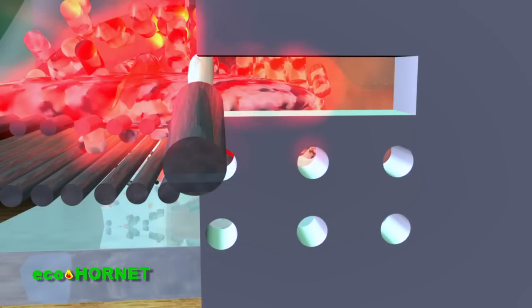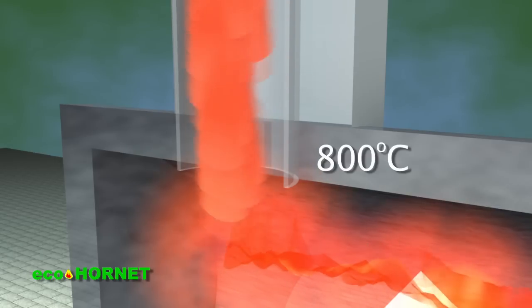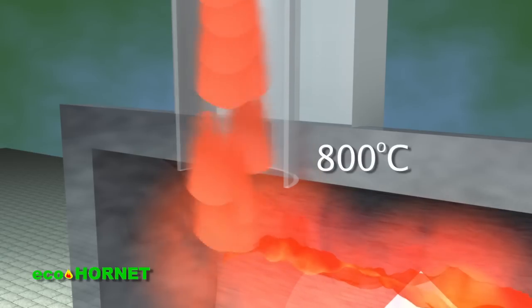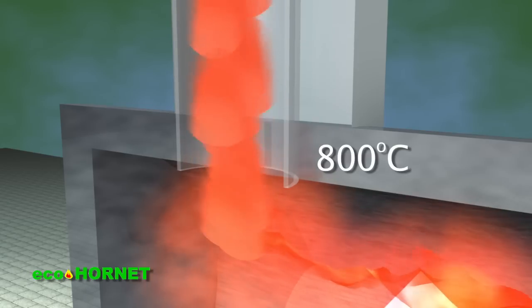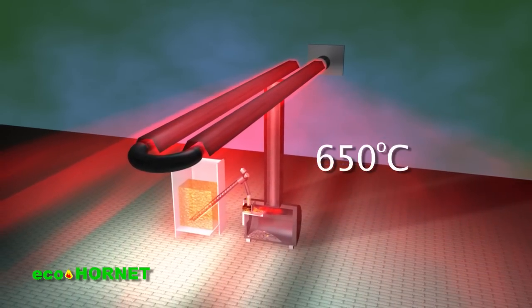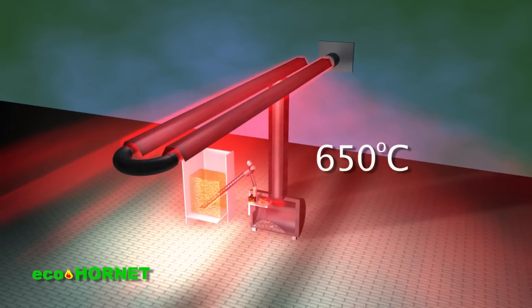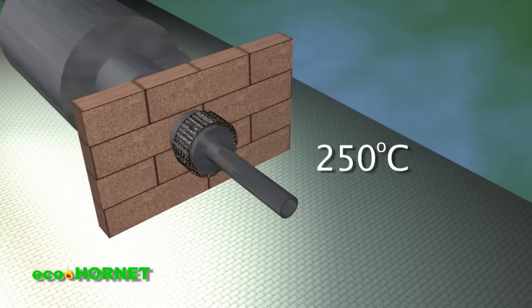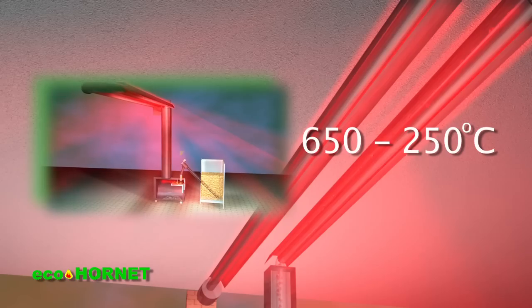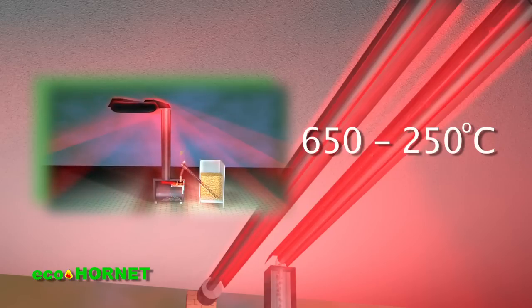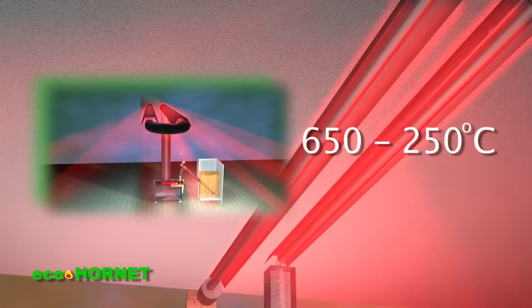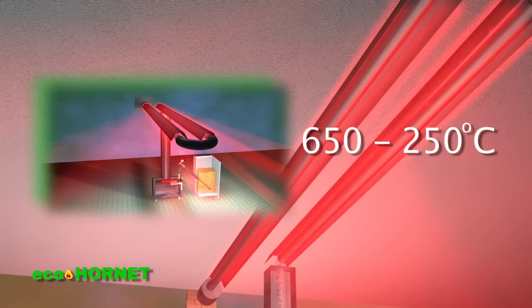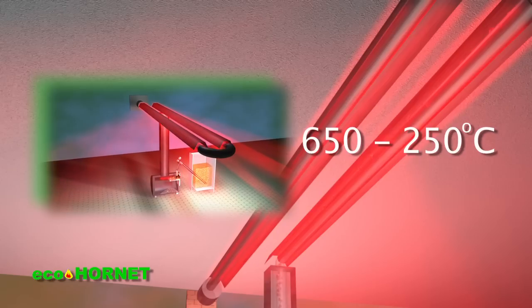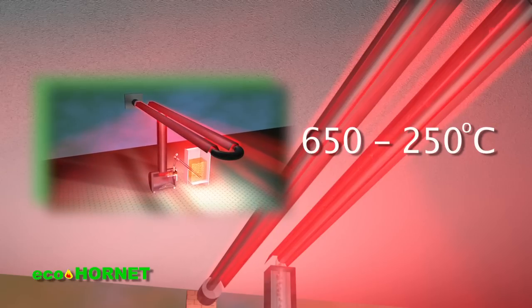The pellet combustion temperature of 1000 to 1150 degrees Celsius is reduced by dosing secondary air, and upon entry of the burned gases into the insulated routing tube, their temperature does not exceed 800 degrees Celsius. Upon reaching the radiant tube, it is 650 degrees Celsius, and it reaches no more than 250 degrees Celsius at the level of the exhaust system. The distribution of temperatures in the radiant tube between 650 and 250 degrees Celsius ensures the uniform heating of the space in which it was located by infrared radiation sent to the ground by the projector located above the heated tubes.